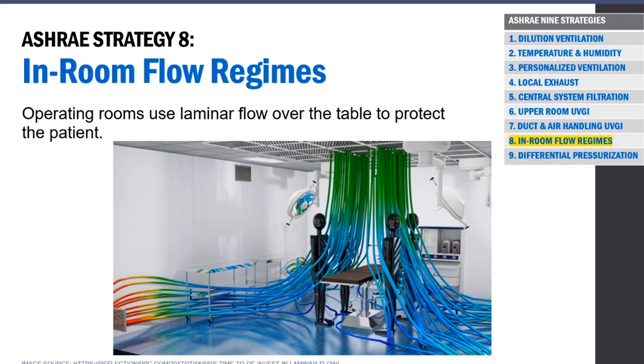This is the computational fluid dynamics configuration of an operating room with laminar flow from top to bottom. The idea is to bring air in at low velocity, somewhere between 50 to 100 feet per minute. We don't want higher velocity because it impinges dust into the patient's open wound, or the wound may dry out. We want to wash the surgeon's body with air and exhaust it at the lower level. This approach is here to stay, unless you think otherwise.